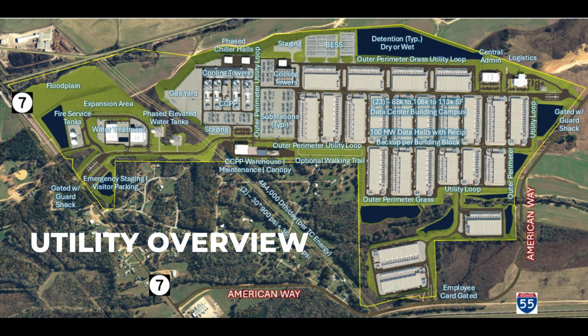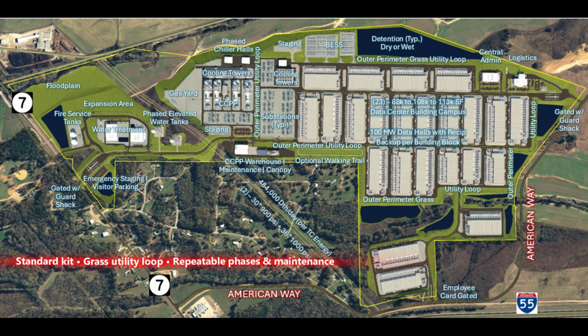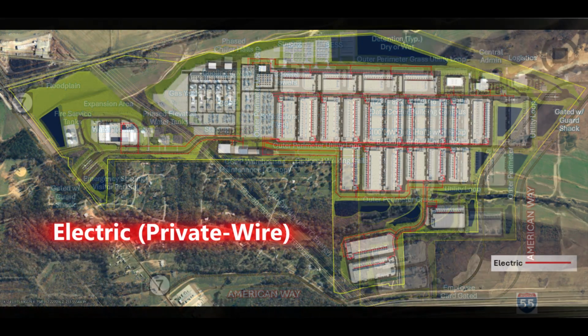Utility overview for the Grenada AI Energy Campus. The Grenada AI Energy Campus runs on a standard playbook, repeatable building footprints, and copy-exact utility kits. Loops sit in the grass utility grid with sectionalized tie points, so crews follow the same steps pad after pad. Shorter routes, fewer pavement cuts, faster phases, and a predictable O&M. A low-water central plant that leverages secondary chiller heat for efficiency completes an overall design providing high availability without complexity.